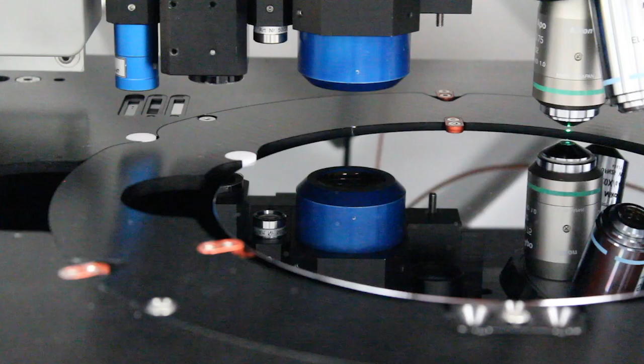Even with TTV sensors on top and bottom looking at each other can lead to false readings. FormFactor utilizes polarizers to neutralize light passing through the wafer. With measurements on top and bottom surface, we deliver total 3D capture of the wafer thickness. This helps in determining global wafer parameters with high throughput. Now, what other types of silicon carbide wafer measurements does your metrology solution provide?